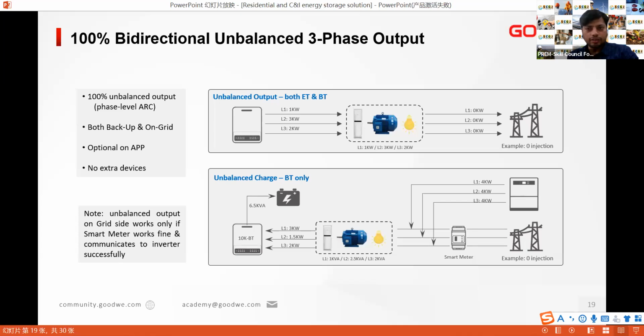But sometimes they connect resistive or inductive loads that create problems during high surge currents when the system is turned on, and suddenly the inverter gets tripped. So that's the problem that normally happens, and that's the reason I asked this question. So normally the manufacturer recommends connecting a balanced load on all three phases of the system.